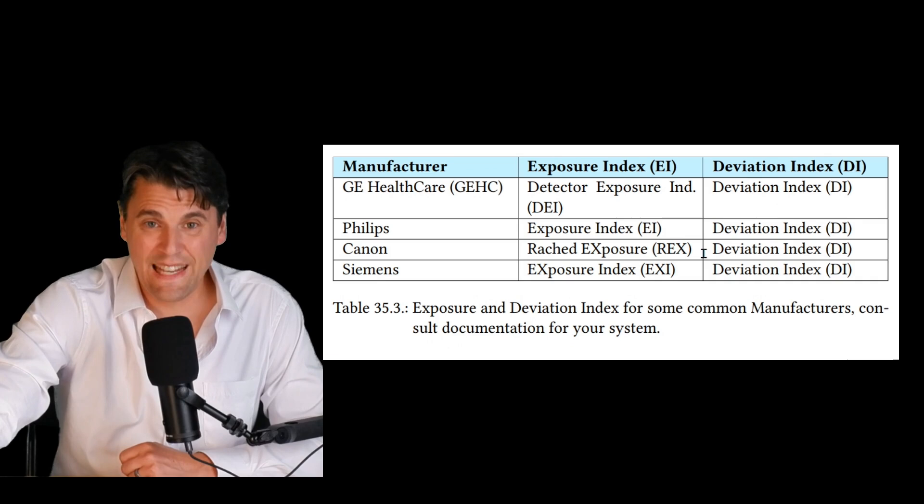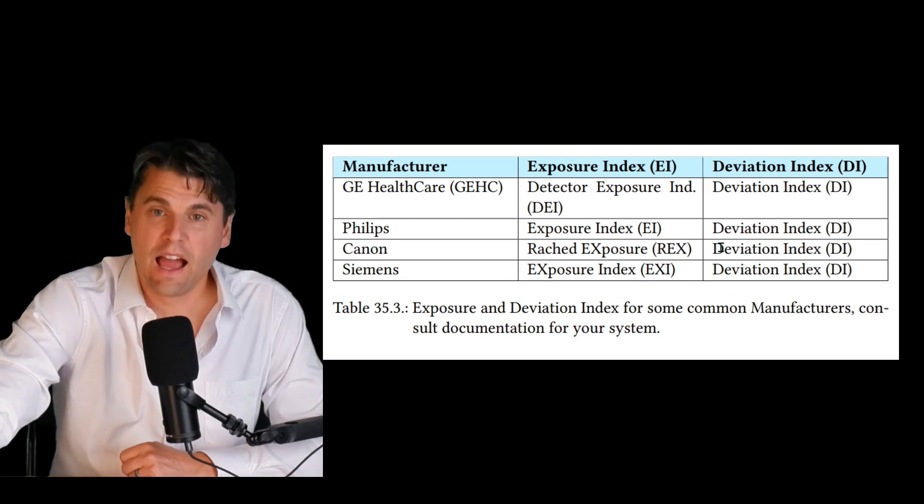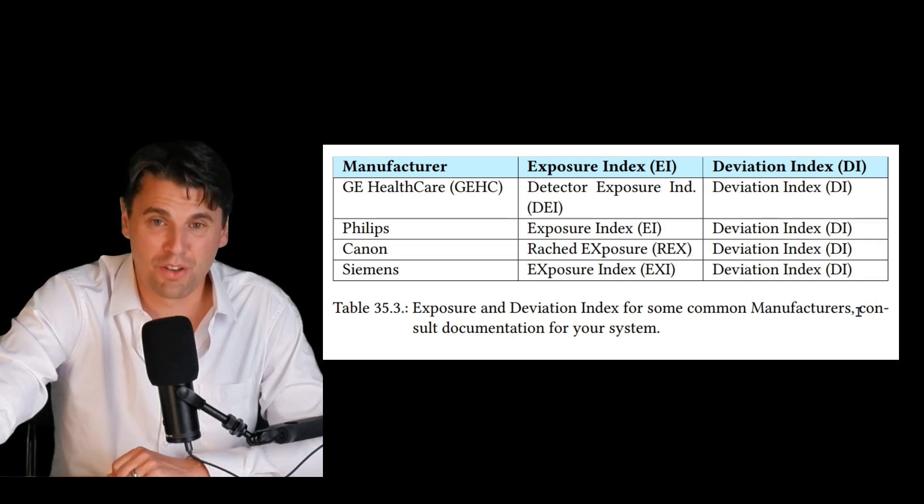Canon uses reached exposure index or REX. Siemens uses exposure index or EXI. And then luckily on the deviation index, all the vendors have used the same DI or deviation index in order to denote the deviation index. On your UI, these are the values you're going to be looking for, for the different vendors.